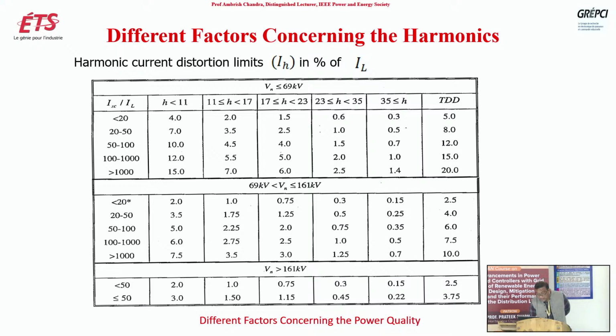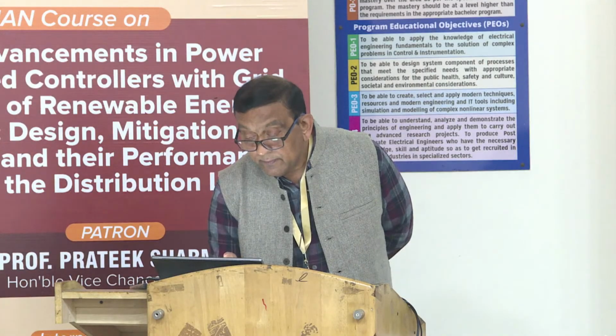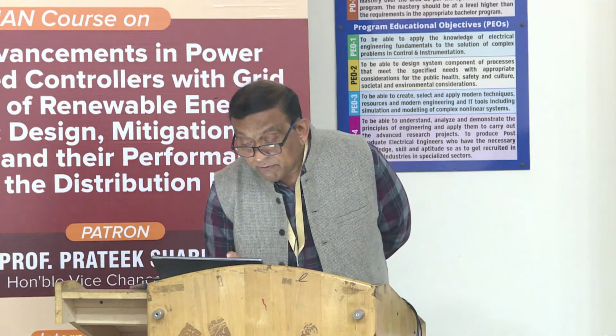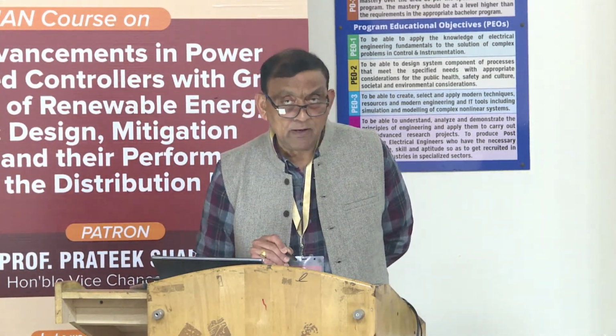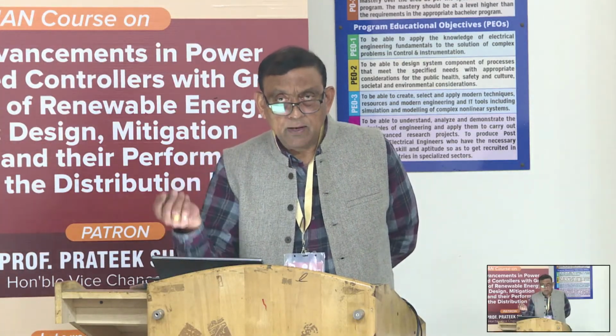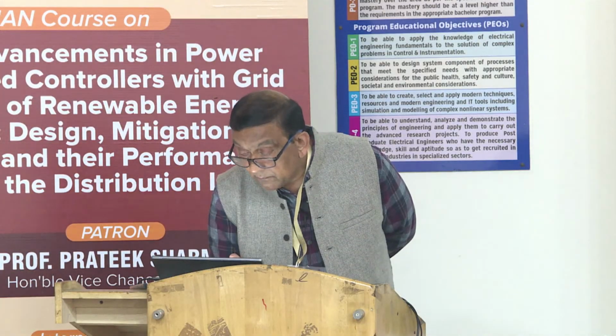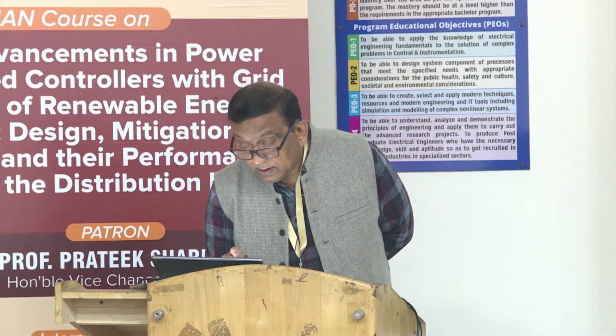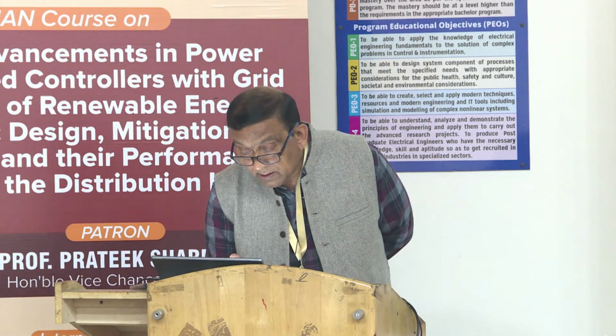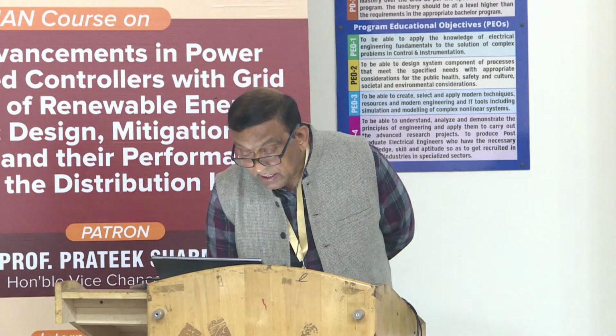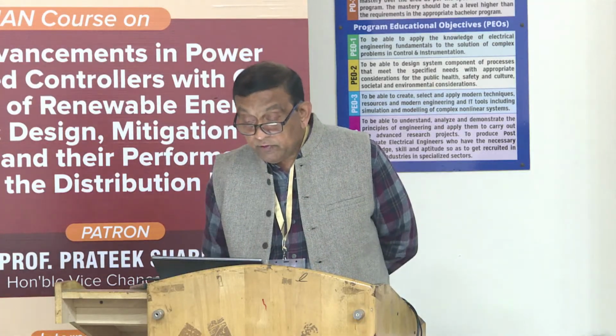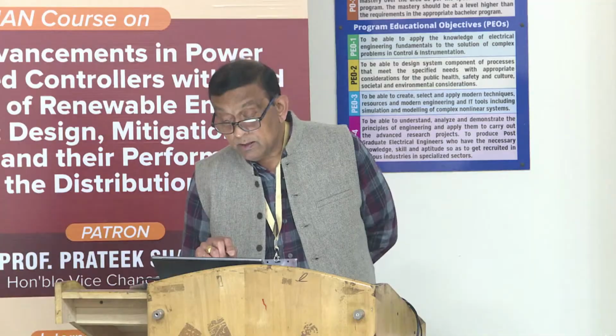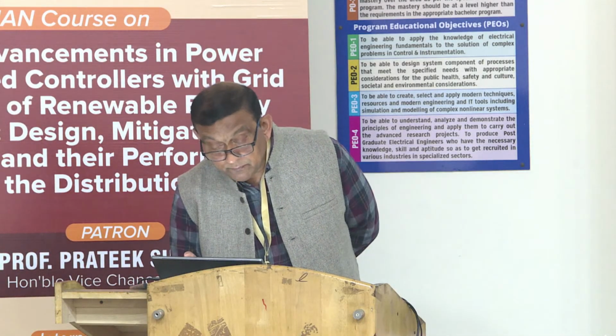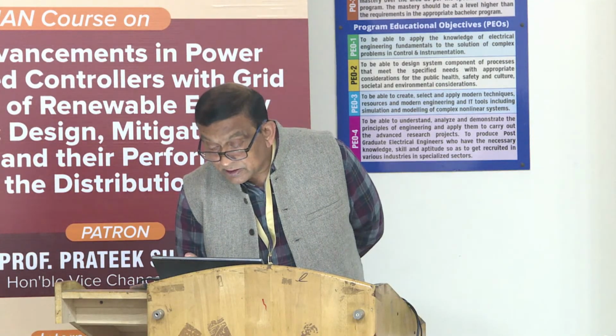So that's why you see starting from less than 20 ratio, it may be more than 1000 here. And this is how the limits are changing here. If harmonic is less than 11th harmonic, like 3rd harmonic, 5th, 7th, up to 11th harmonic, this is 4% for individual harmonic. And then if size of the system is increased, we can go to 7%, for larger size 10%, and if the size is more, then we can go to 15% individual harmonic, while total you see is still for a smaller system 5%, and then for larger systems this limit is increasing.